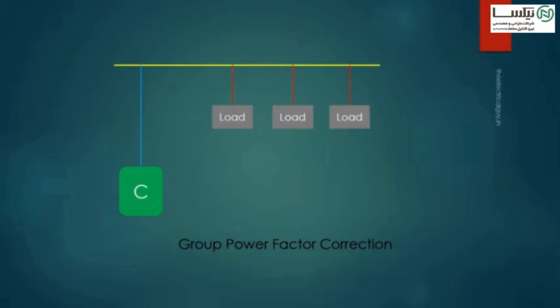Group power factor correction. This method is generally used for the loads which have similar functioning. A common capacitor bank is provided to improve the power factor as shown in the figure. So for example, if you have 3 similar induction motors which are being used for the same purpose, you can use a common capacitor bank for power factor correction. This method is also economical but recommended only for small loads.